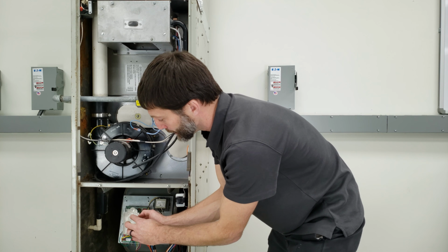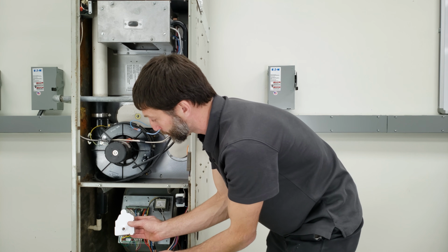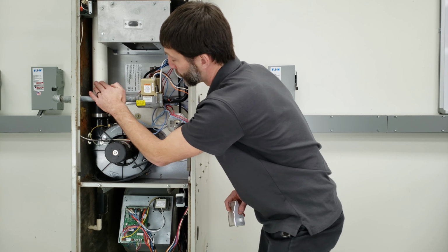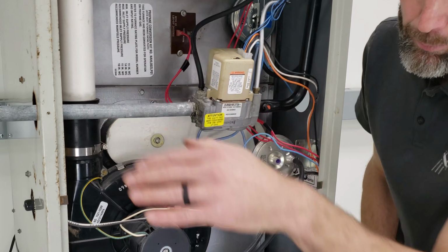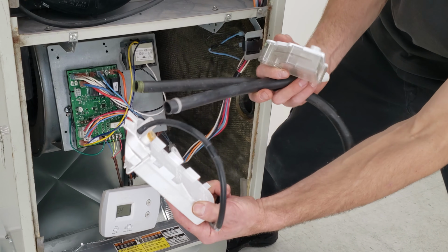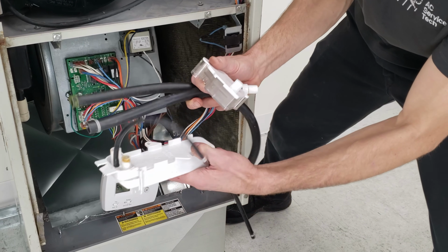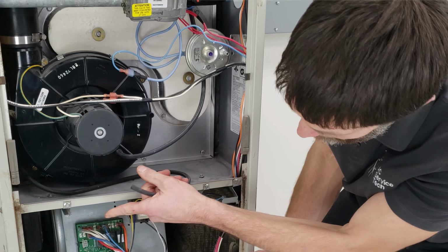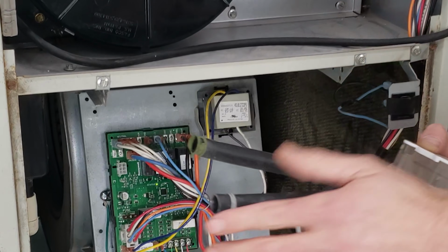And so you need to make sure to either blow out or vacuum out these condensate traps every once in a while, and you need to clean them out. You got to make sure that you have proper pitch for your exhaust pipe, about a 1/4 inch of pitch per foot going away from the furnace. You also have other types of condensate traps that you can't see into, and so you need to make sure to vacuum or blow them out. And so you want to make sure to disconnect from the pressure switch when you're cleaning out your trap. And so I have another video linked down in the description section below on how to do that.